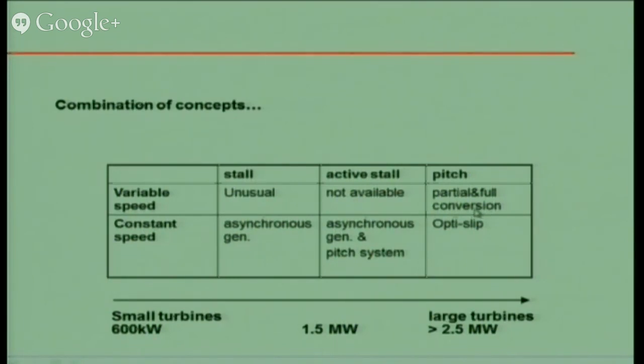These days only pitch is available—partial pitch and full pitch. Constant speed is also there, using an asynchronous generator, and opti-slip is also there for a pitch machine. These machines are available from 600 kilowatts up to 2.5 megawatts. Above 2.5 megawatts, it's only gearbox and DFIG.